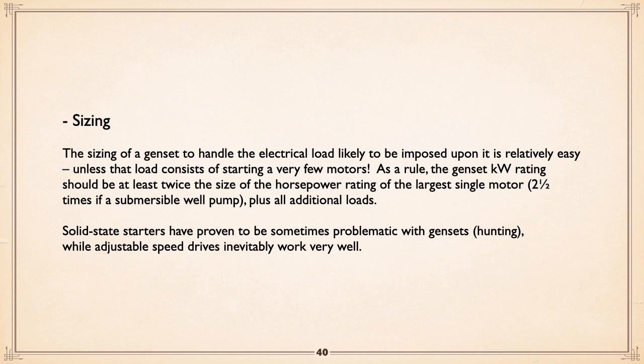If I got three 100 horse motors, I would have 3.5 times, a 350 kilowatt genset. That's kind of sloppy, but it does work very well. And if you spec at that, you're pretty safe. Okay. Solid state starters have proven to be sometimes problematic with gensets hunting. Not quite sure why, but they can be. I warn you that can happen. Adjustable speed, you may even want to oversize the genset a little bit. Adjustable speed drives don't seem to care very much about genset problems. They just don't have them. They work very well with generators, very well.